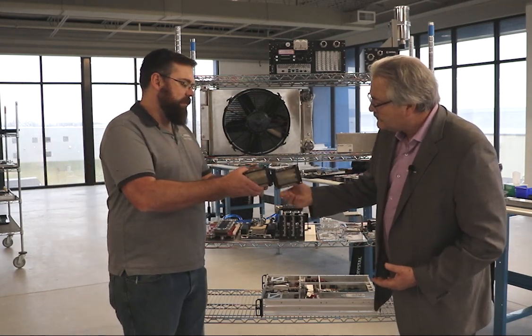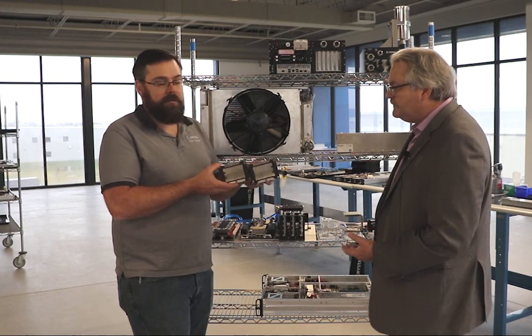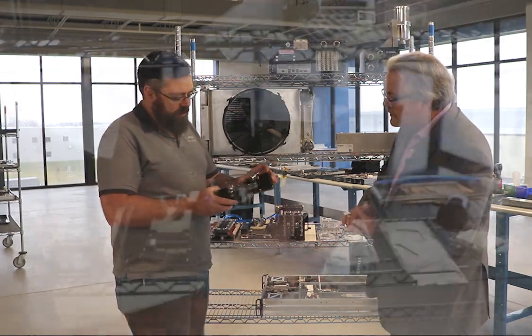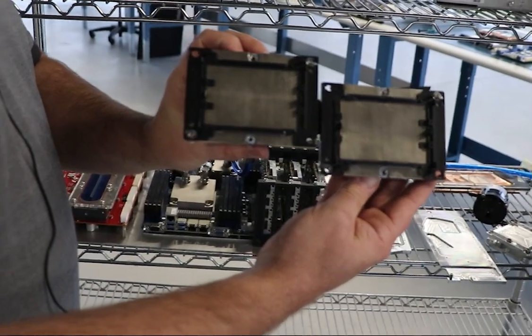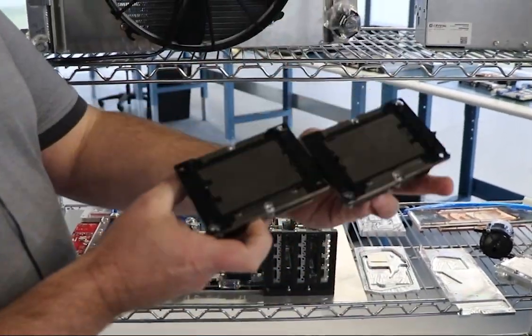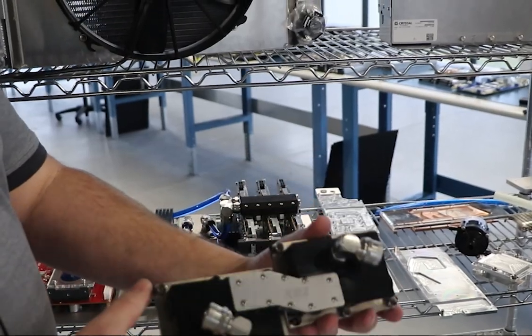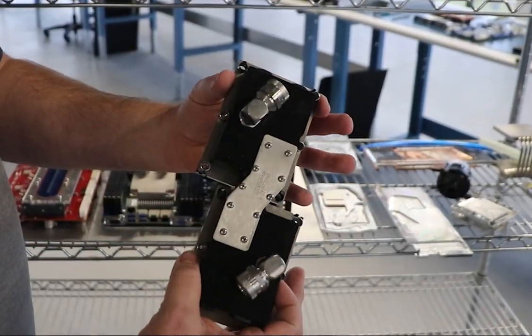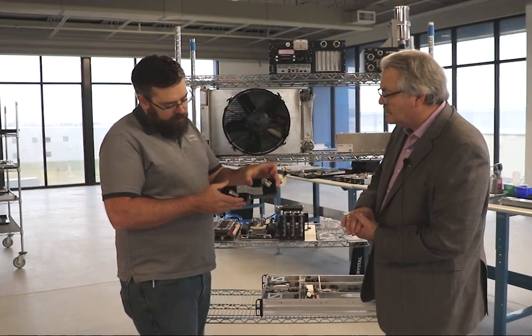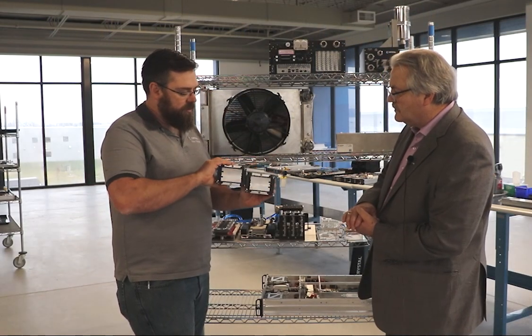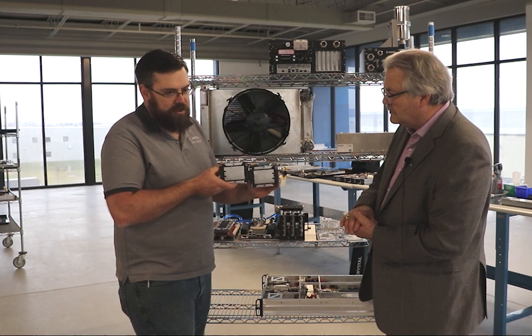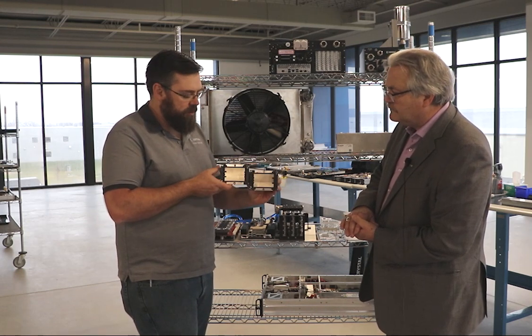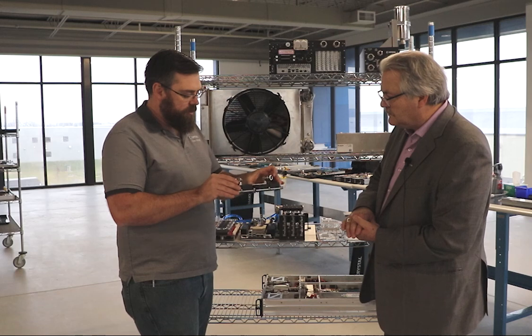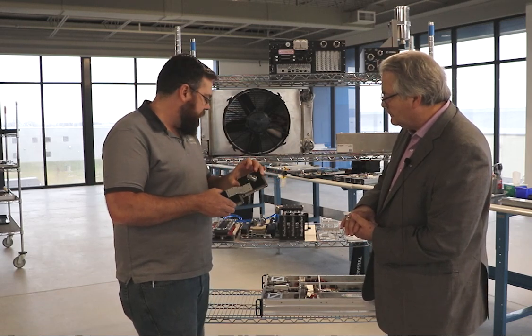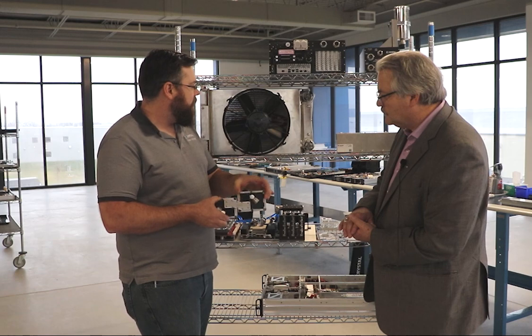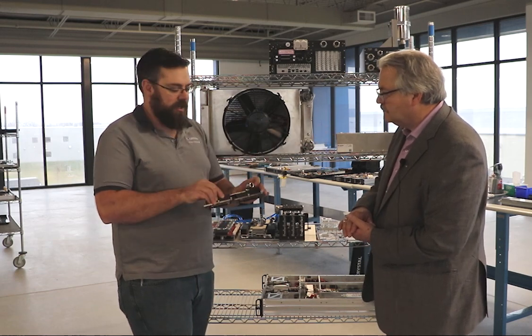No. This is one of the designs we've come up with for a dual socket CPU motherboard. As you look at this design, you'll notice we've incorporated both CPUs into one design, which has eliminated some fittings and interfaces, reducing risk of leaks and creating a lower pressured system overall. With new CPUs, we're seeing wattages of 265 watts per die, creating issues where we can't cool that much heat in a typical 1U or 2U system. So now we're pumping it out to a system like this that dissipates that heat more effectively.